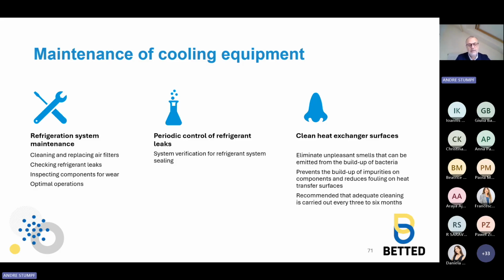In Europe, the F-gas regulation requires a systematic verification of the refrigeration system's sealing. This control is very important to limit direct emission of HFCs and prevent refrigeration interruption. In case of leaks, the quantity of refrigerant in the refrigeration circuit is not nominal, and the energy efficiency decreases. For the same production of cold, energy consumption increases. And lastly, cleaning the surface of the heat exchanger. It's very important. Cleaning is important for maintaining the energy efficiency of the refrigeration system, especially the heat transfer components of the system.